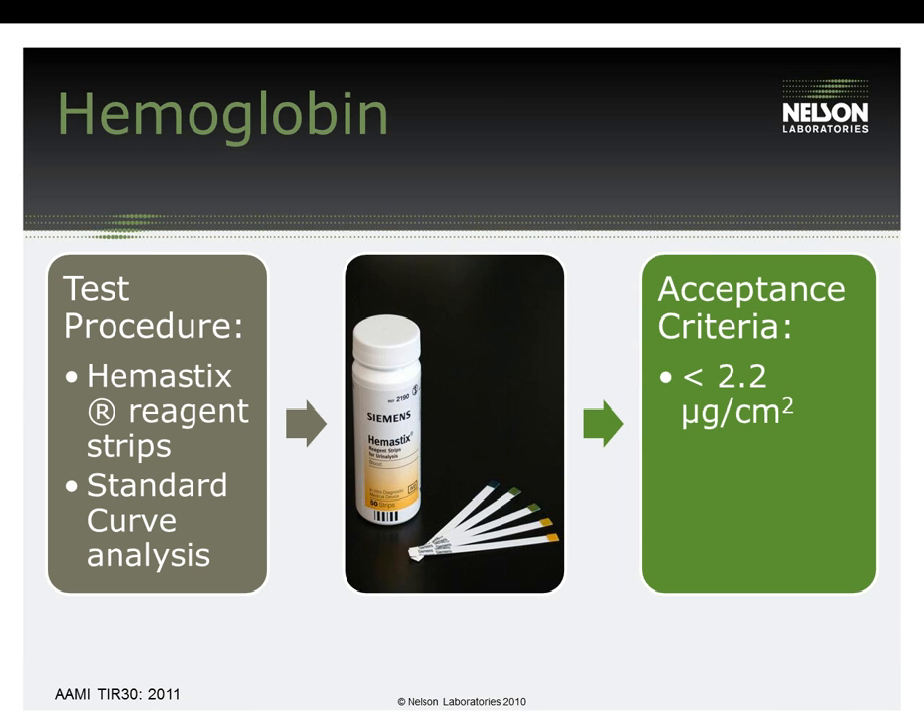Hemoglobin is usually tested for devices that come in contact with blood and has been one of the popular residual testings for cleaning evaluations. The hemoglobin test is qualitative since the analysis is performed by Hemastix reagent strips, but with the use of a standard curve, the results are quantitative and reported as such — this procedure is considered a semi-quantitative analysis. The limit of detection is 0.5 micrograms per mL and the acceptance criteria outlined in TIR-30 is less than 2.2 micrograms per centimeter squared.